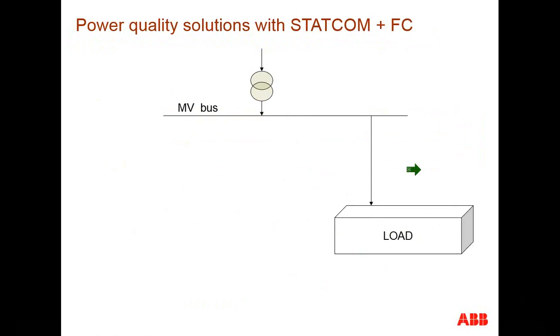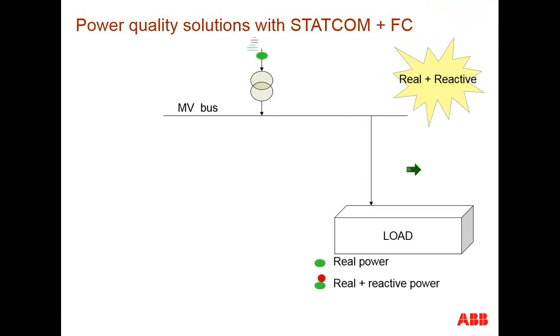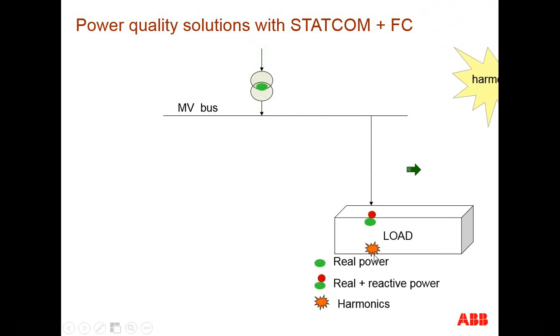Here is one pictorial view of how power quality is affecting the user. You can see normally we need basically the green active power, but because of the nature of the load, it is a combination of both active as well as reactive. So red reactive power also started coming, and recently because of the introduction of power electronics in drives, UPS and so many other loads, converters and all, we also produce harmonics. So from outside, the transformer doesn't look like it has so much pollution in terms of the electrical network.